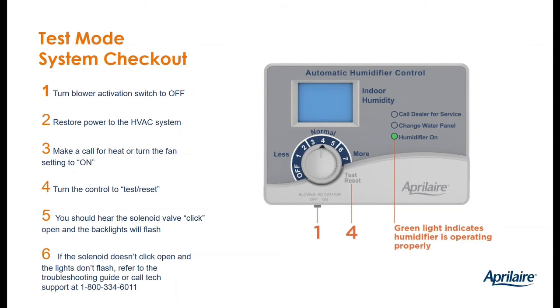If you leave it in test mode, remember, test mode's only good for 1 minute. Test mode's only good for 60 seconds. If you leave it in test mode, at the end of test mode, the solenoid valve is going to close and it's never going to run again.